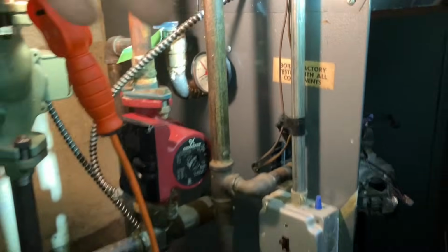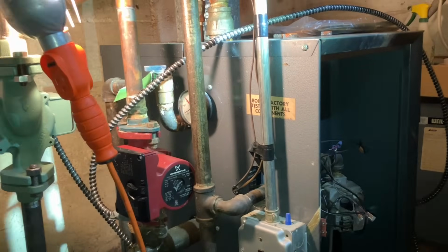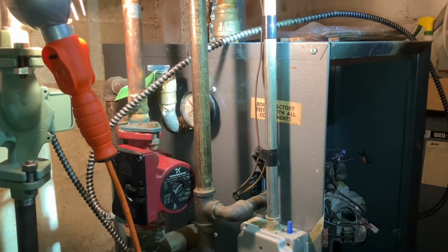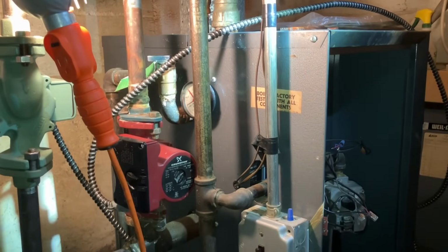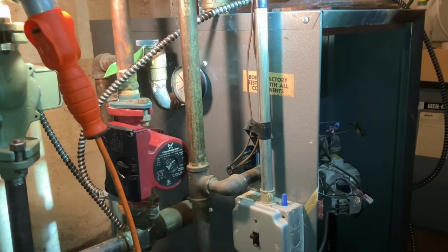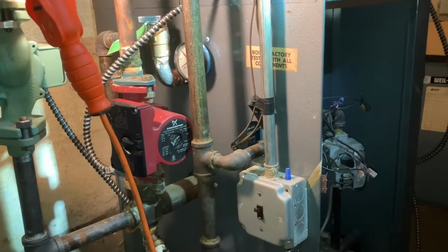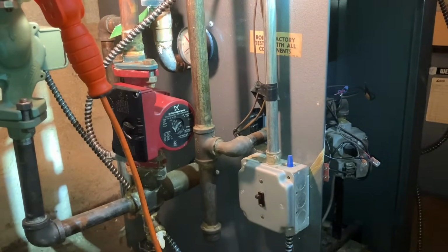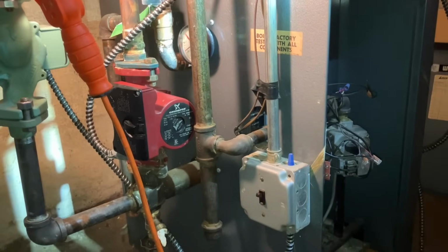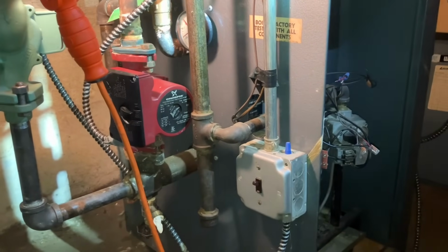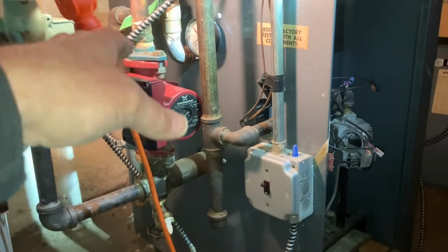So here's a common misconception. You said at the beginning of the season you drain the boiler out. There's no need to touch anything in the boiler, unless there's air being introduced into the system during a service, so something was disconnected, the system was repaired, the system was drained, refilled. You don't need to take the water out and replenish it, right? It's a closed system, and unless there's a leak, that automatic feed valve there will just maintain pressure.